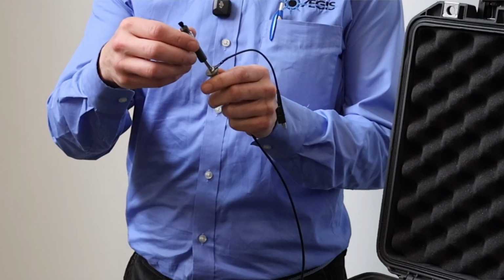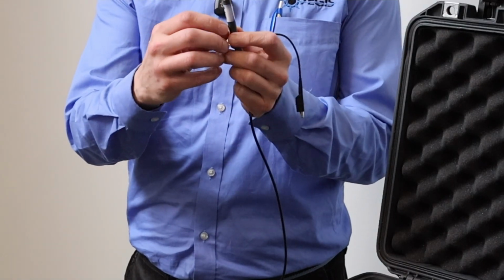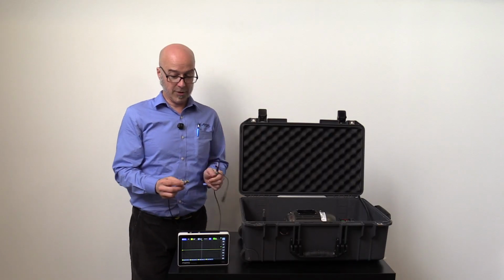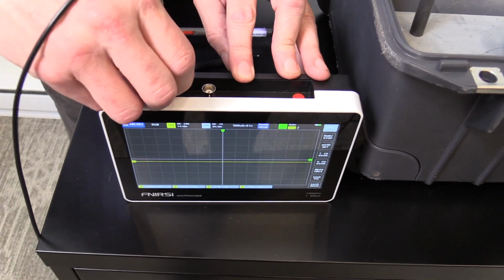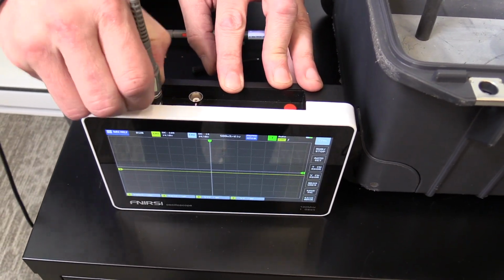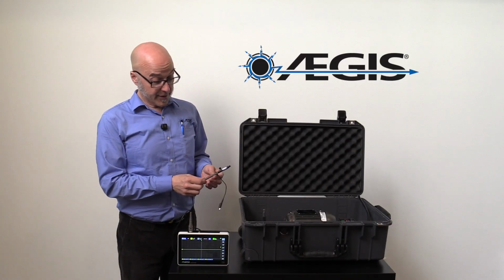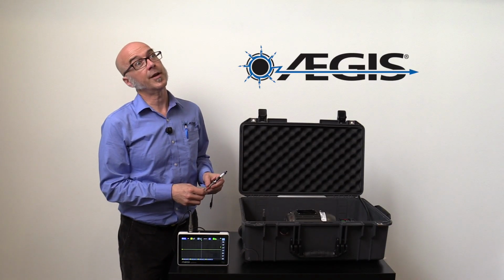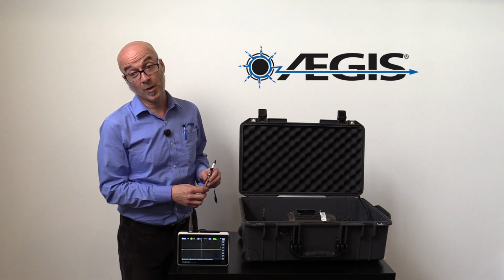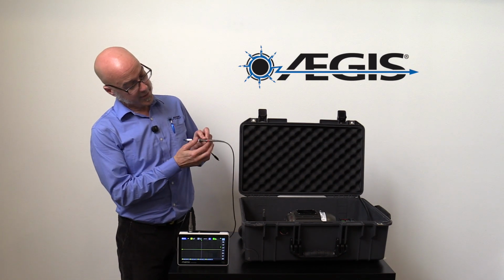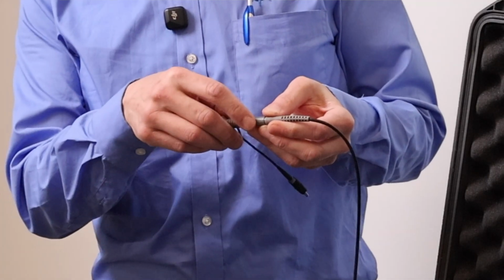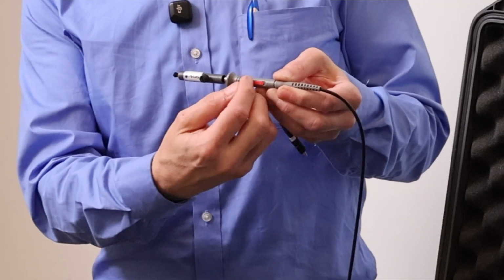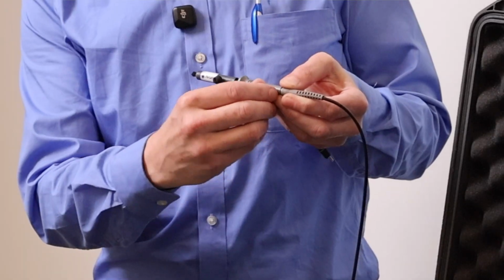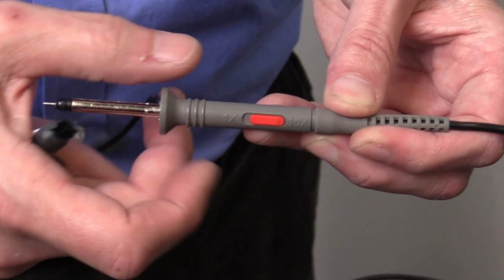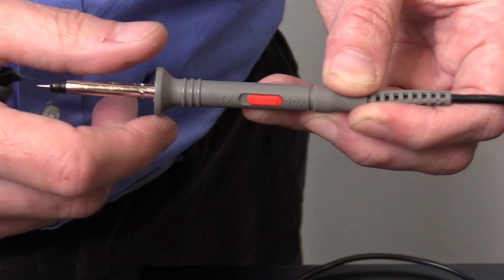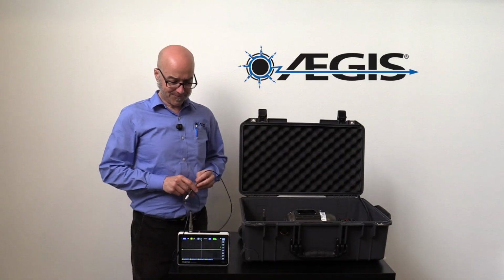You just slide it on down the barrel and then tighten the set screw. All right, next step, we'll plug into channel 1 on the top of the scope here. The next thing to do, very important, something like 90% of all the errors we see are caused by missing this. Check the attenuation. This probe has a little slide on it. When it's toward the tip, it's at 1x. In the other direction, it's 10x. We always use 10x or 10 to 1 when measuring shaft voltage.